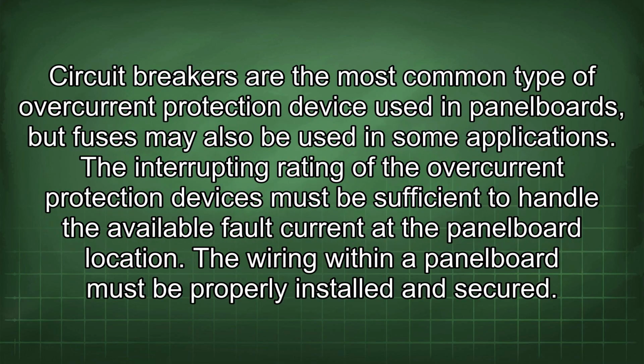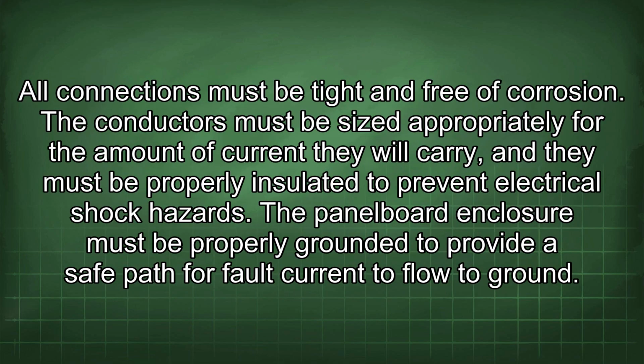Circuit breakers are the most common type of overcurrent protection device used in panelboards, but fuses may also be used in some applications. The interrupting rating of the overcurrent protection devices must be sufficient to handle the available fault current at the panelboard location. The wiring within a panelboard must be properly installed and secured. All connections must be tight and free of corrosion. The conductors must be sized appropriately for the amount of current they will carry, and they must be properly insulated to prevent electrical shock hazards.